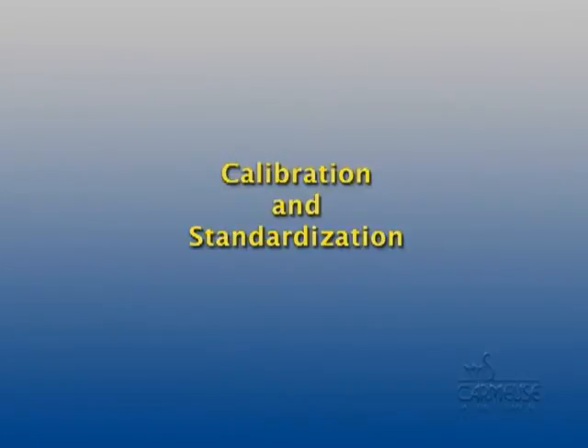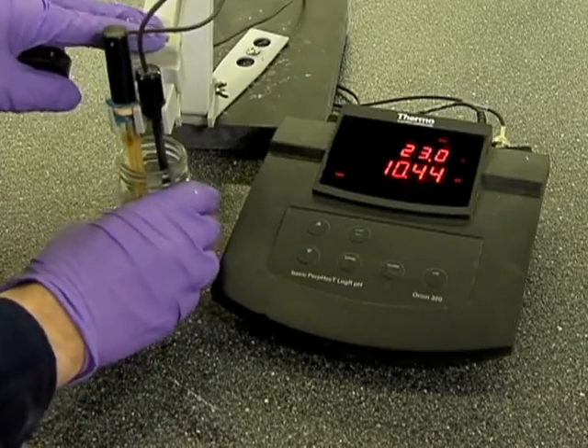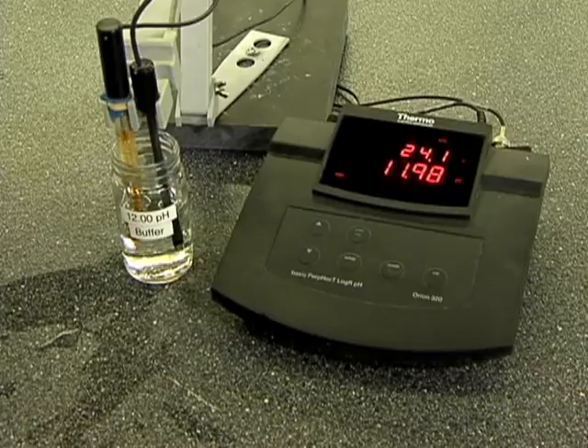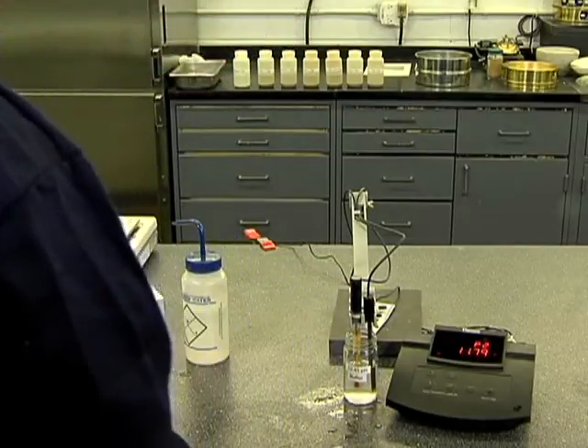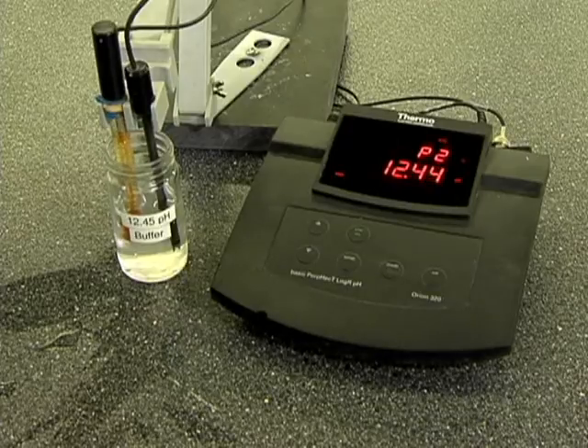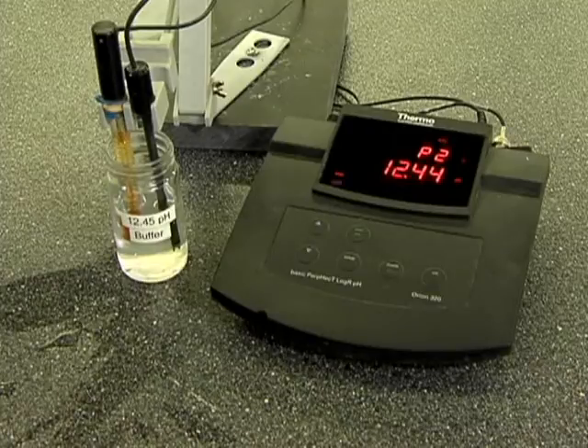The next stage of the test method is calibration and standardization. The current specification allows the pH meter to be calibrated using a 12.0 pH buffer solution at 25 plus or minus 1 degree Celsius, or to follow the test method described in section 11.2 of ASTM D-1293 to create a calcium hydroxide buffer solution equal to a pH of 12.45. However, Carmeuse has found that calibration by a single 12.0 pH buffer does not offer the best results. For improved results, calibration should bracket the anticipated pH, and Carmeuse recommends a two-point calibration using both a 10.0 pH buffer solution and a 12.45 pH buffer solution.